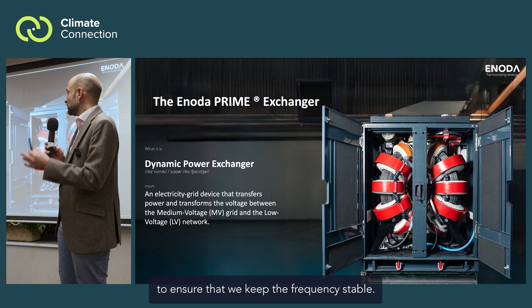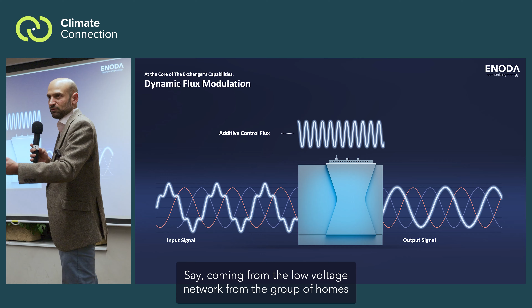We do that through something called dynamic modulation of flux through near-field induction. I wasn't planning to talk about this, but Julia wanted me to explain it. So here on the left-hand side, you have an input signal, say coming from the low voltage network from a group of homes. And on one of those phases is a nasty fifth harmonic that might have been created, for example, by a cheap inverter on a rooftop solar array. If that harmonic propagates up the network, the carrying capacity of those poles and wires will be reduced by up to 30%, and today we don't have a good way to fix it.